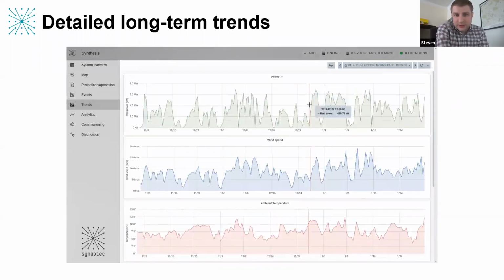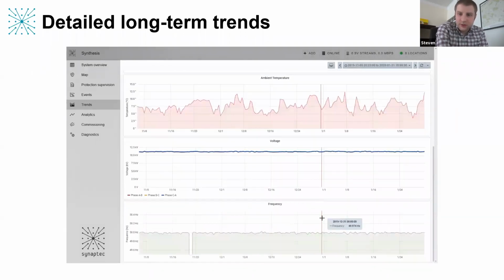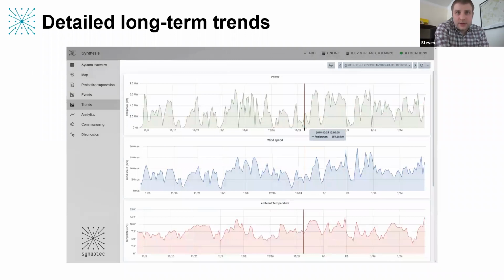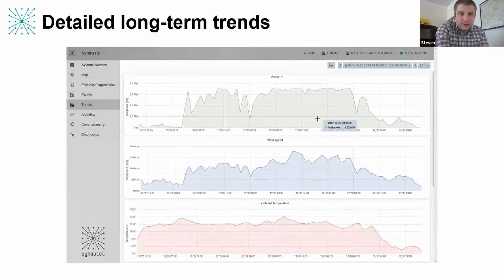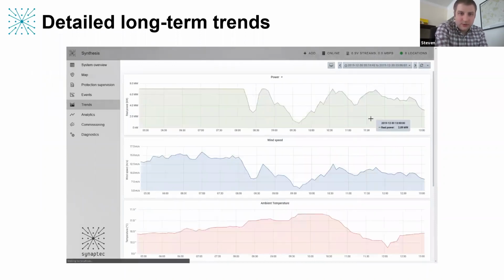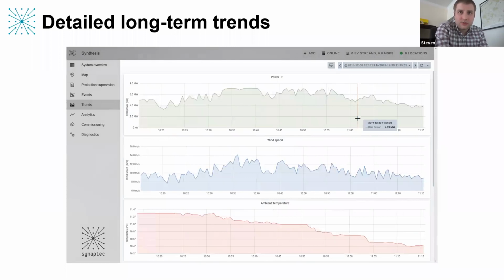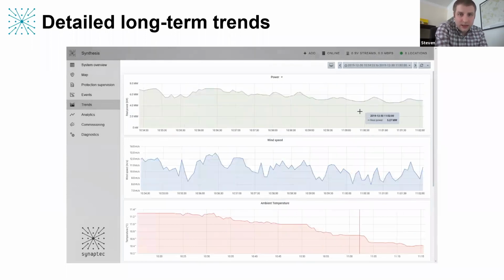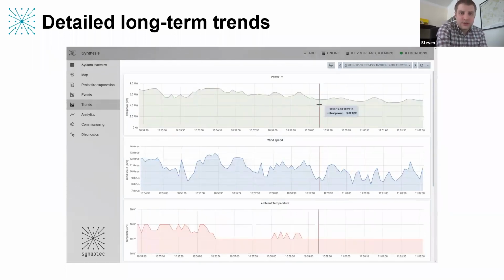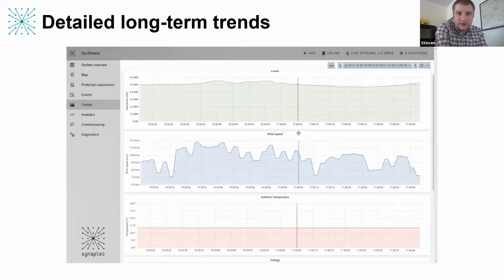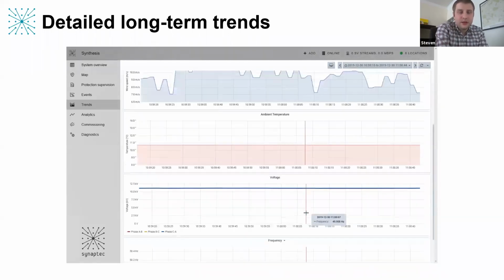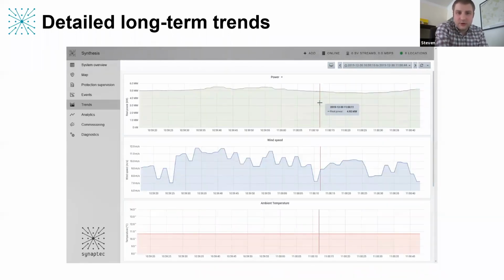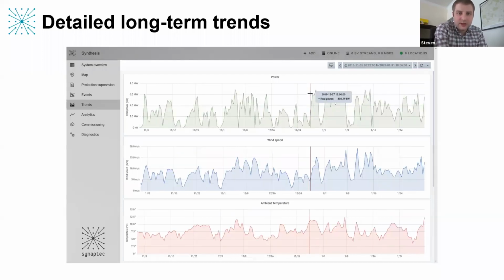We can also look at different harmonic signatures over time and see if there are any anomalies. If any of the harmonics change over time, we could flag that up because it might be due to an underlying mechanical issue, something with the controller of the power electronic converter, or an issue with the filter, or any of the above. So it allows a detailed view that wasn't really possible before because the costs of implementing it were excessive.